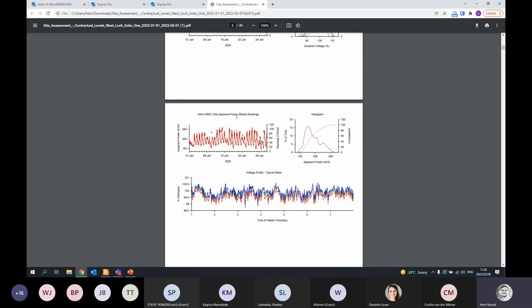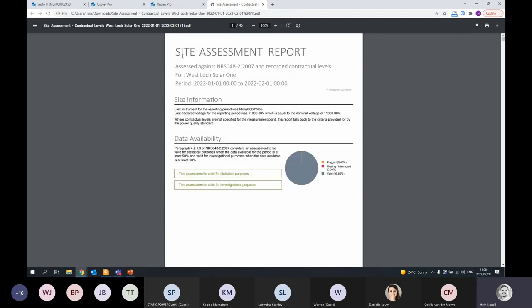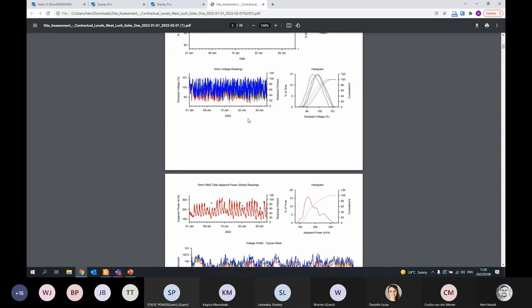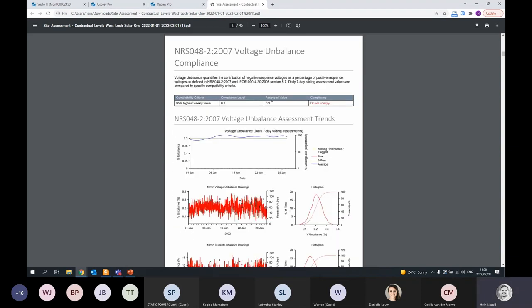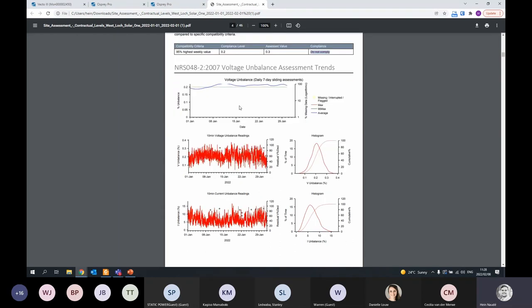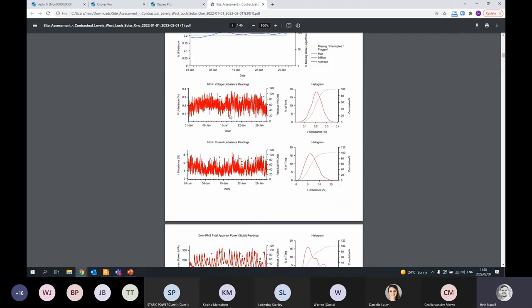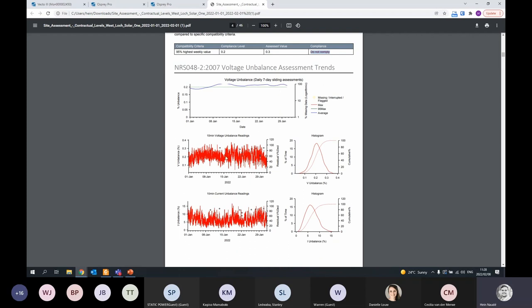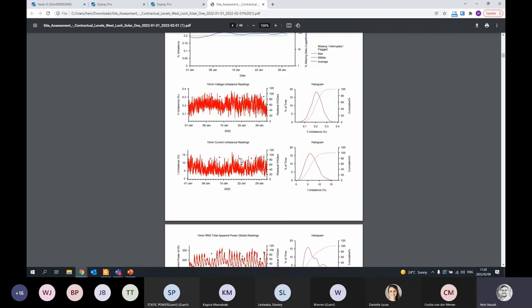This report I actually set up based on the contractual level. For this specific meter point, I created specific limits just to test it - for example, I set the unbalance limit to 0.2%. You can see this measurement is not complying, it's exceeding that unbalance, and you can view the 10-minute trend over the last month that we've scheduled it for.